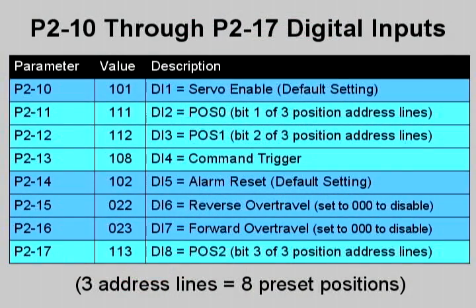One additional note about the digital inputs. The most significant bit selects normally open or normally closed. We've chosen 1 or normally open for all of our inputs, except the over travels. Over travels are generally wired normally closed as a fail safe.